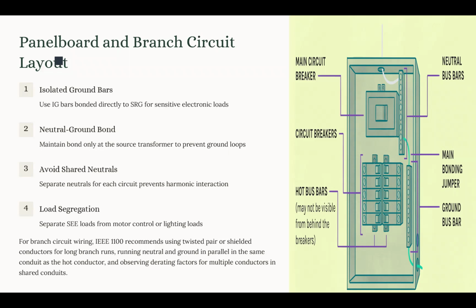Now, another requirement for those panel boards is to avoid shared neutral. We have to provide a separate neutral conductor for each branch circuit. So if you have a nonlinear load that generates triplen harmonics, like the third harmonic, ninth harmonic, or 15th harmonic, those do not cancel in the neutral, but actually add up arithmetically. If we have a shared neutral, it could lead to an overheated neutral conductor. So we have a fire risk here, or we could have voltage distortion and noise coupling between those circuits.